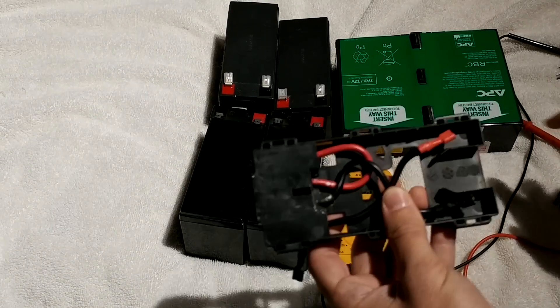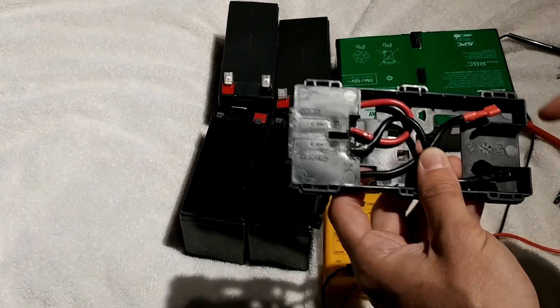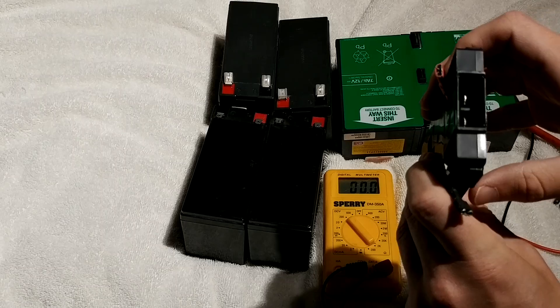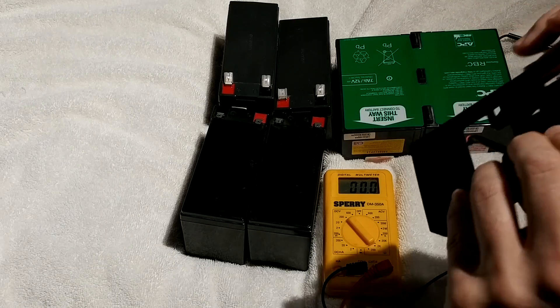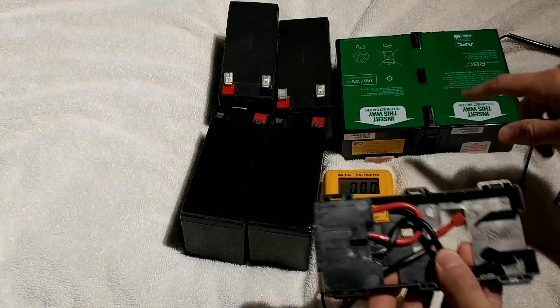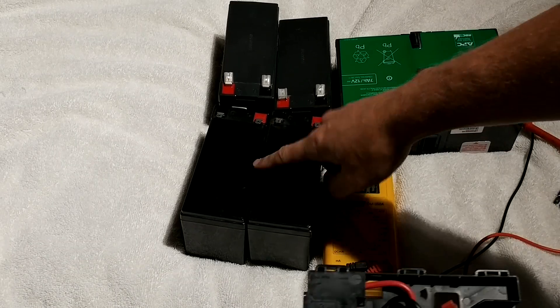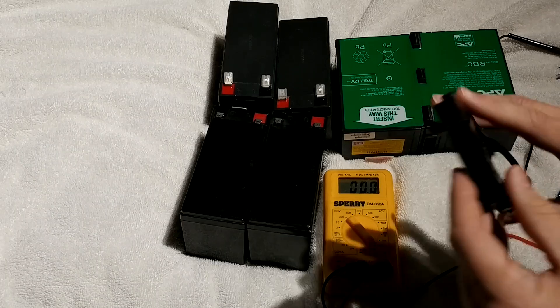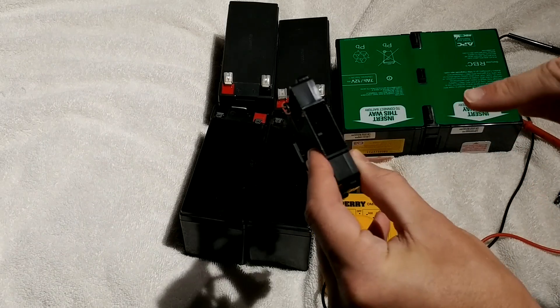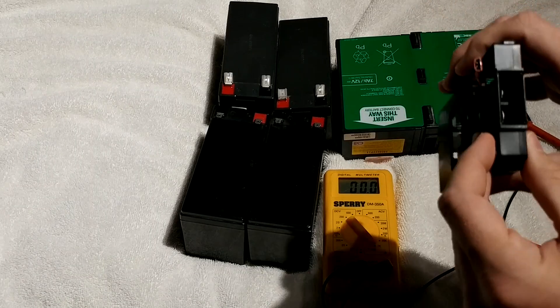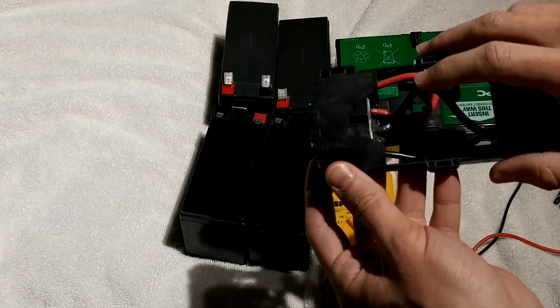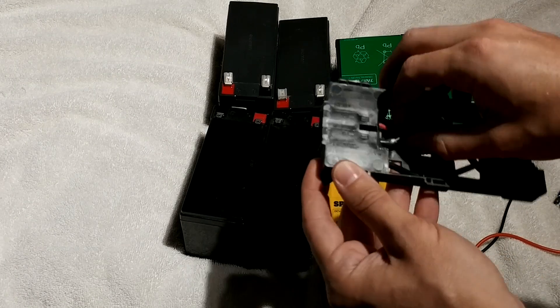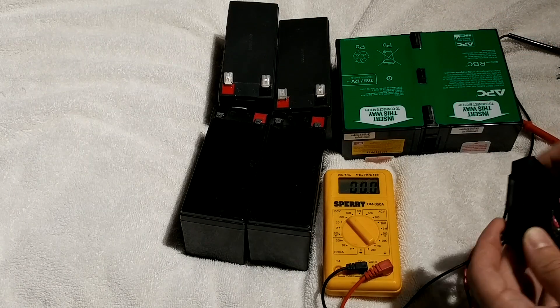This is the battery cell connector that joins the two separate cells and connects them to the UPS unit. There's two spade connectors in there, faintly labeled black and red. One battery goes on this side and they're connected in series, and one battery goes on this side. The problem was one of the spade connectors in there was loose and wasn't getting connected in the UPS unit. So what I did was use some epoxy to firmly seat that in there so they don't wiggle and they stay straight, true and easier to connect in the unit.